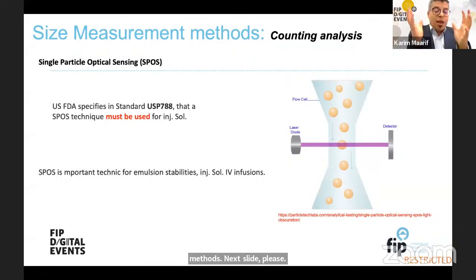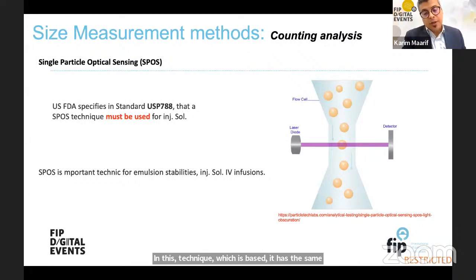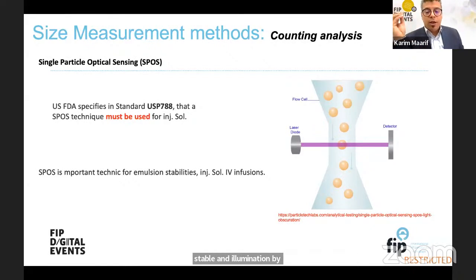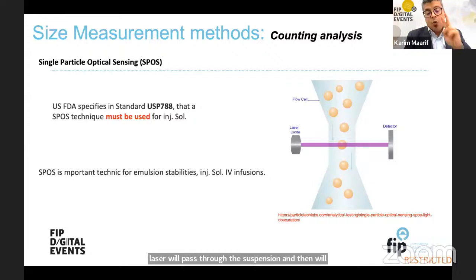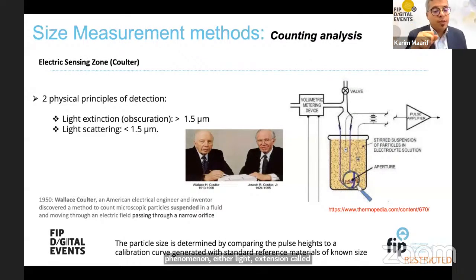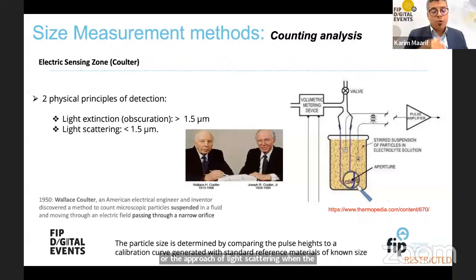In single particle optical sensing, which has the same concept as the Coulter system but without an electric field, particles in suspension move in an area with stable illumination by laser. The laser source passes through the suspension to measure the particle size. We distinguish two phenomena: light extinction called obscuration when the particle size is higher than 1.5 micrometers, or light scattering when the particle is below 1.5 micrometers. Both approaches are used in the same equipment.